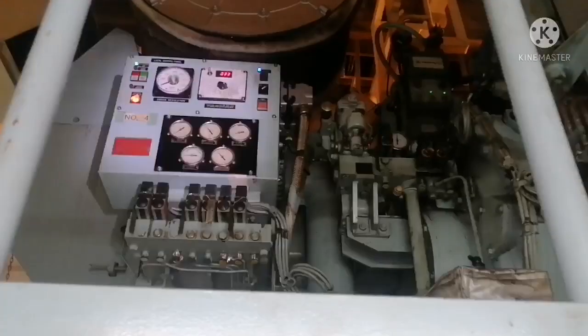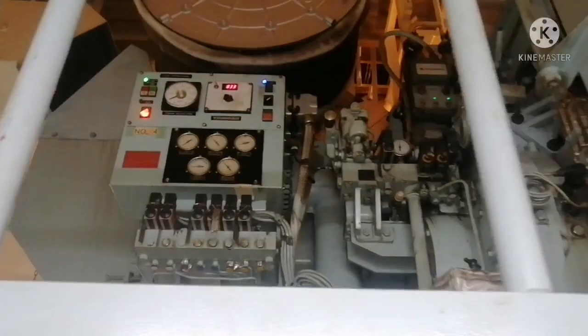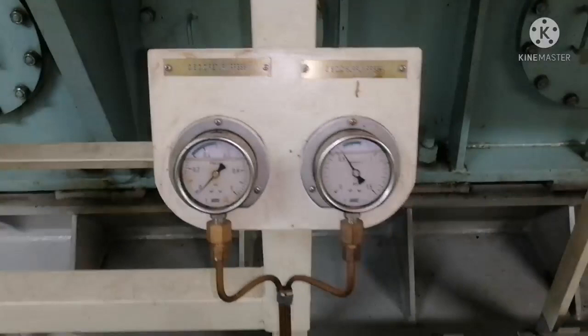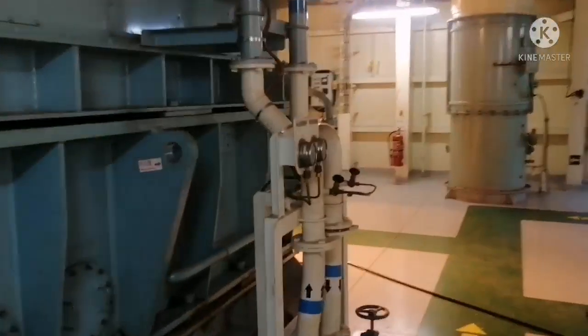For the generator which is not running, you have to check whether the lube oil priming pump is running and the engine ready to start light is glowing, and also you have to check the lube oil sump level, and you have to check the cooling water pressure at the outlet and everything.